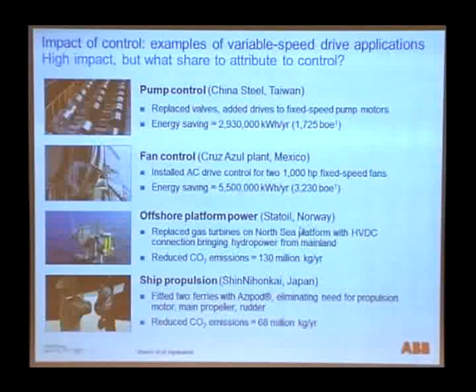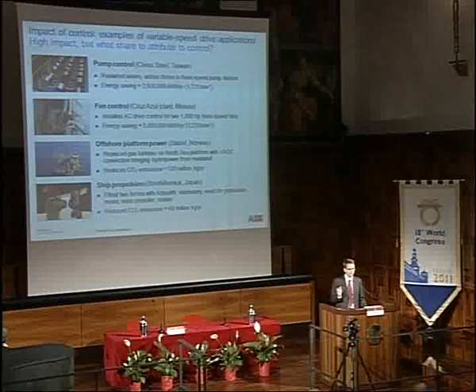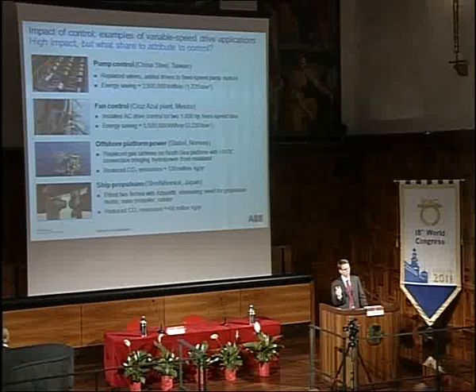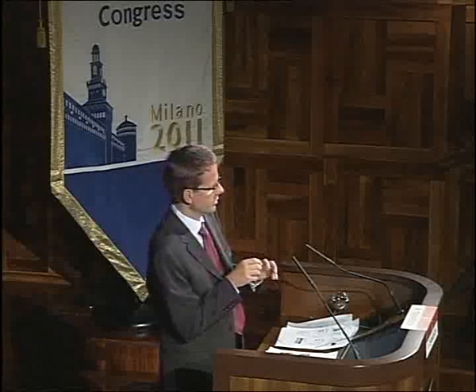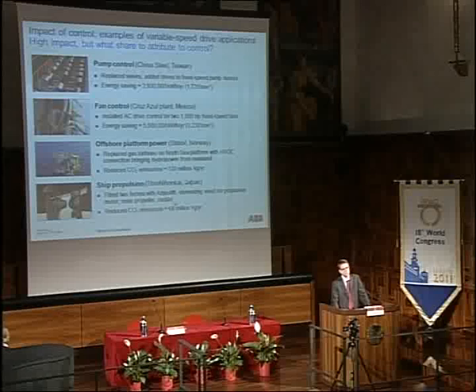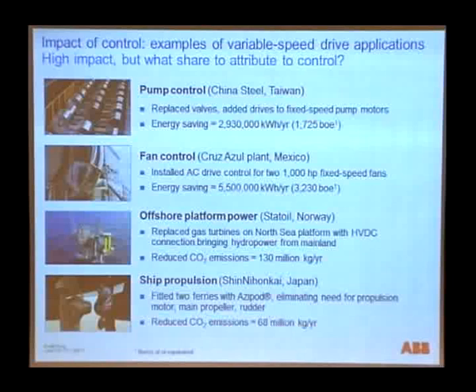On the other side, you also get what I'd almost call engineering miracles built with this as a building block for a rather new concept. What you see here is an offshore platform in the North Sea, offshore Norway. Norway essentially has hydropower, so it's very clean power there. To run the gas compressors on this platform, you bring in high voltage direct current from shore, and then you immediately use the receiving terminal as the drive for some very high voltage motors. So that's a device that in a combined way executes a high voltage DC receiving terminal as well as a drive control function in one actuator, so to say. That's rather neat, and it's been running for about 6 or 7 years now, really a benchmark in the industry.